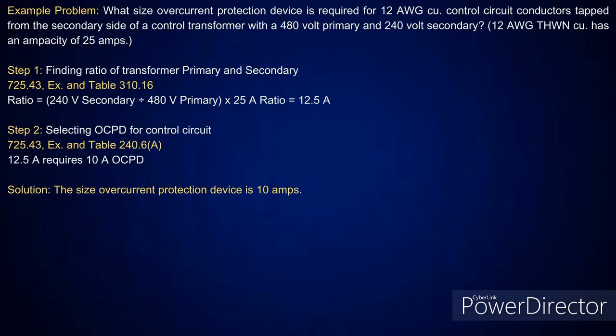So what I need to do, and you'll remember this, where we're tapping, I said always when you're tapping, you've got to get what? The ratio of the transformer. So I would take the 480 volts divided into 240 volts. We're telling you here that the number 12 has an ampacity of 25 amps. So take that ratio of the transformer times 25 amps. That's going to give you 12.5 amps. And then I'll drop down to the next standard size overcurrent device.